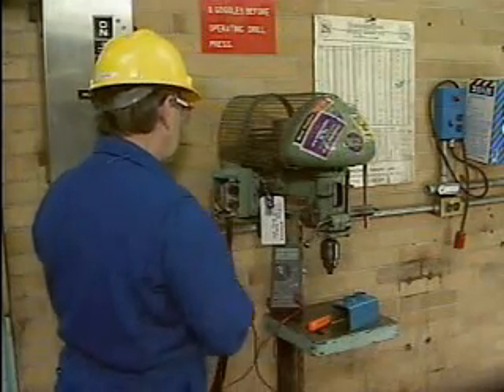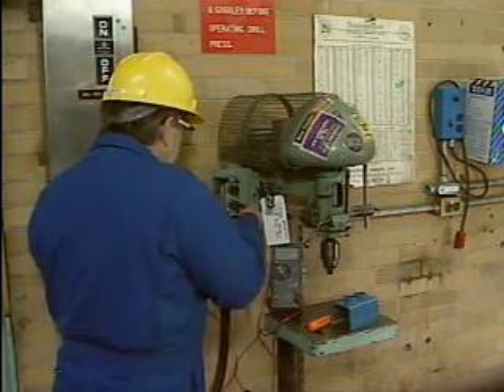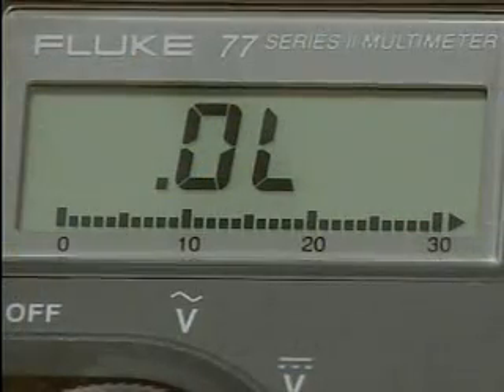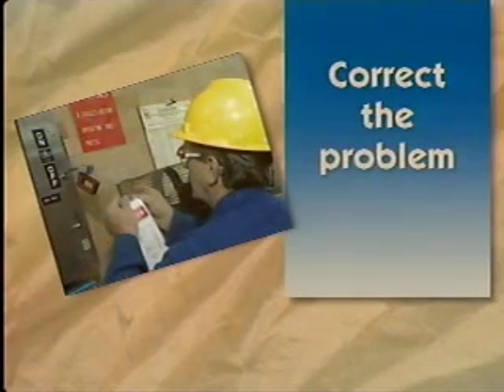The electrician connects the test probes to the contacts of the stop switch. The multimeter indicates that the stop switch is open. Under these conditions, the multimeter should not be indicating that the normally closed stop switch is open. Since the electrician has determined that the cause of the problem is a defective push-button switch, he can move on to the next troubleshooting step, which is to correct the problem.